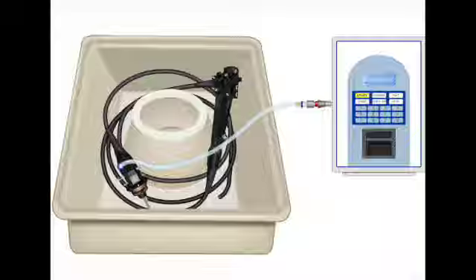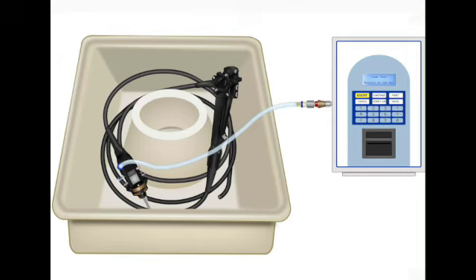And it relies more on the technician, I'm guessing? Entirely. The prep is the same. Remove the parts, hook it up. But instead of a machine, you have a hand pump with a pressure gauge. You pump it up yourself. You pump it up to the required pressure, and then you do the exact same physical manipulations. You turn the knobs, press the buttons, all while watching that little needle on the gauge. And if the needle drops? If the pressure drops, it fails. Scope goes for repair. If it holds steady for the required time, and you can't rush this, it passes. It's effective, but yes, much more room for human error.